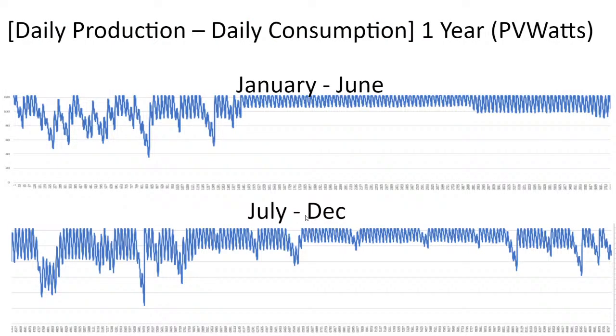We're going to talk a little bit more about that. But for sizing loads, it really is best to get a picture of what the actual load you're trying to size looks like, and not rely on the spec sheet items, because devices use their energy differently than the spec sheets suggest. Is that amperage rating the rating of the device when it's always on, or does the device power cycle up and down?